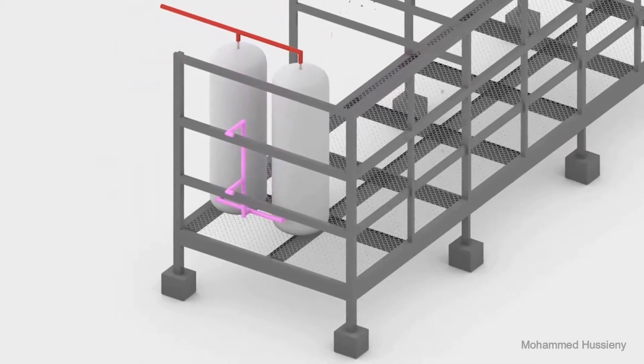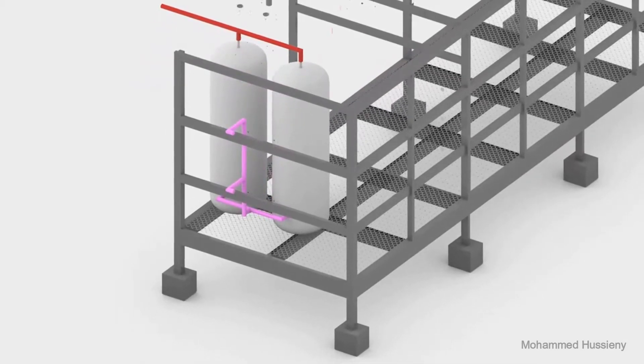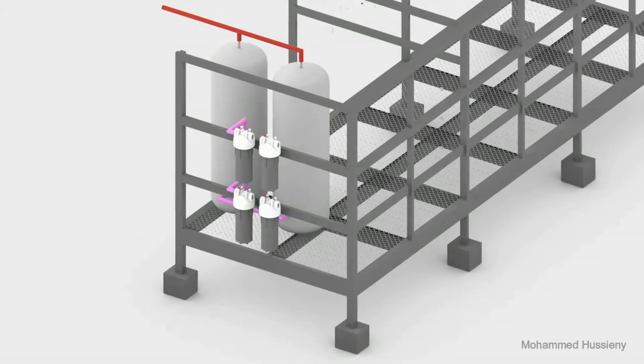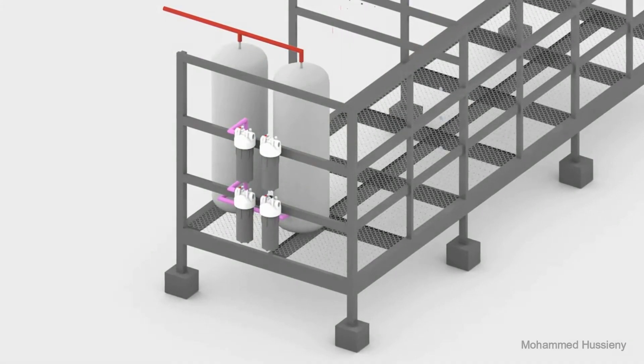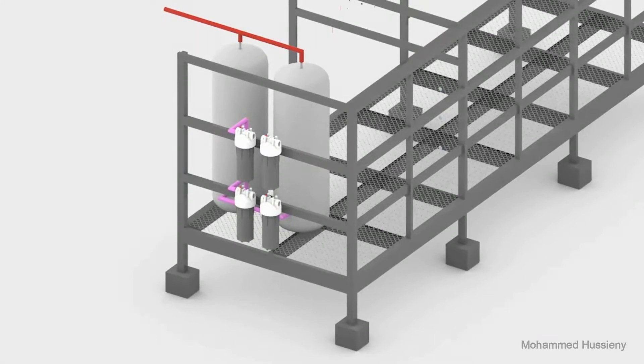Then the produced water is filtered in the micro-cartridge filters in series, which removes the residual suspended micro-particles from water, with pore sizes of 20 and 5 microns.